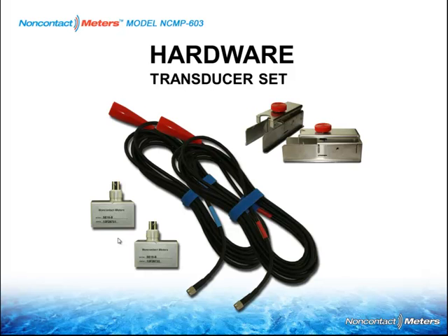The flow range for this equipment is basically from 1/10 of a foot per second to 40 feet per second. It is a bi-directional technology, so you can read to the left, you can read to the right, you can read to the positive, you can read to the negative. The operating temperature of the transducers is -40 to 300 degrees F, which is also -40 to 150 degrees C. The mounting kit includes the transducers and these clamps. These clamps right here are like stirrups. You'll see in the next picture there's a stainless steel hose clamp that goes through there, and the transducers get put in here. The end of the clamps is the same dimension as the end of the transducers, which lets you measure the differential. So you strap these stirrups on and you plop the sensors right inside the stirrup, so it's relatively quick to put them on the pipe. As standard, you get 12 feet of cable with quick disconnect connections, and it comes with a tube of grease, and you're all set to go.